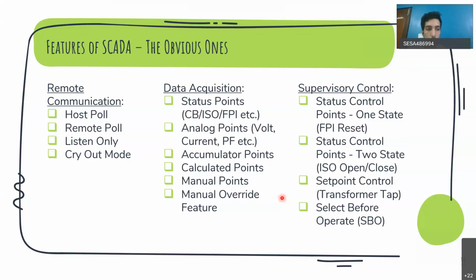We'll talk about the obvious ones first. Obviously it is used for remote communication. This remote communication can be done in different ways. One of them is host poll. Generally, this is used where your control center is polling the data - control center is requesting for data from all substations and RMUs, and they are obliging. So that is the first type. Remote poll is reverse: substations and RMUs are pushing data on their own and control center is receiving it.